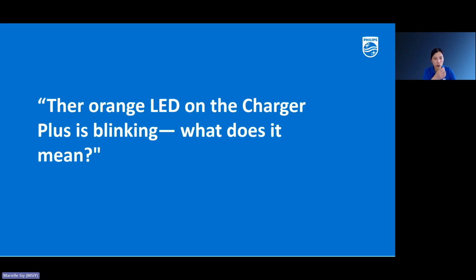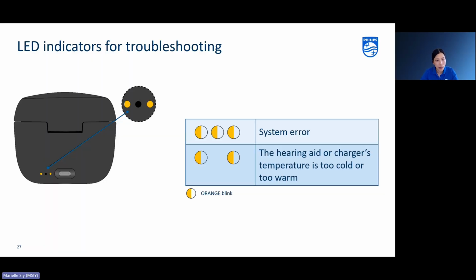What about if the orange LED on the charger is blinking? What does that mean? It depends again on the pattern. There are two distinct orange LED patterns on the Charger Plus that indicate different issues. The first pattern is the one that you see at the top. If all three LEDs are blinking orange, then this means that there's a system error in the charger and it needs to be replaced.